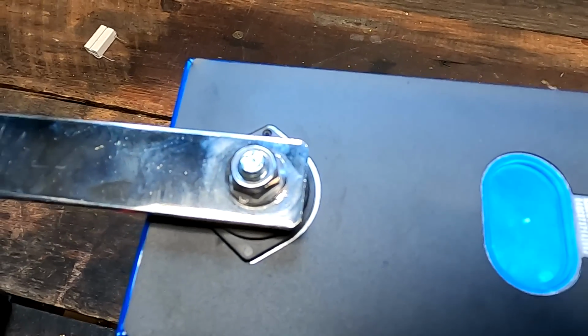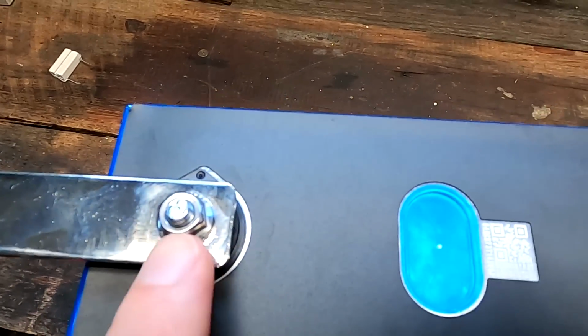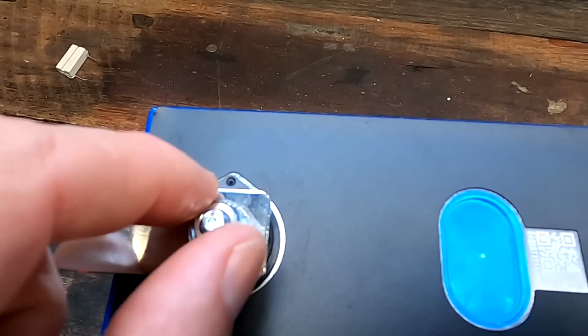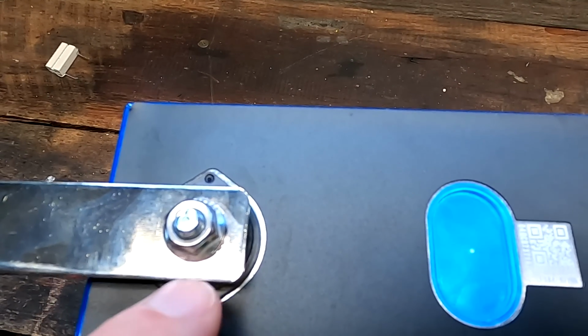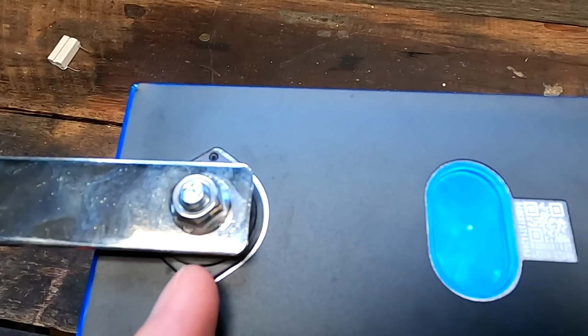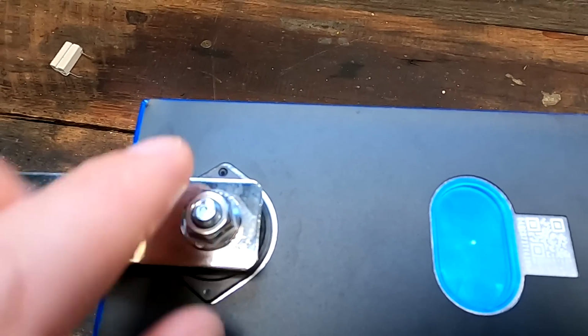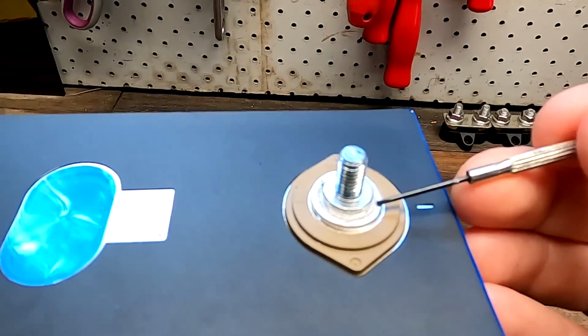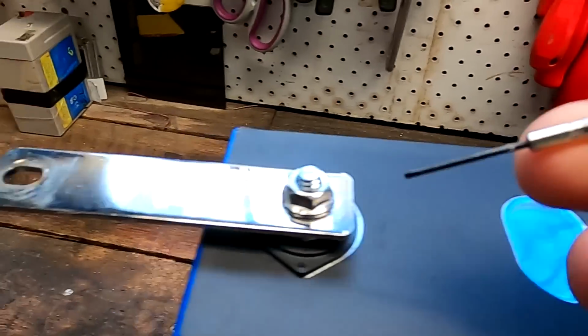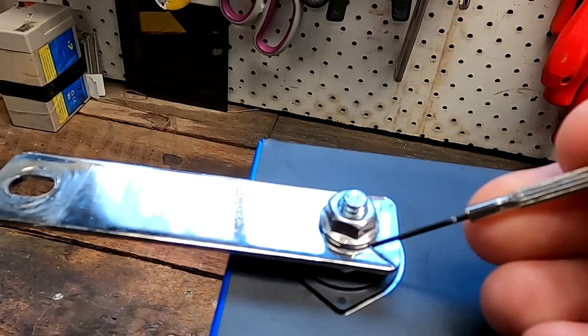Another frequent comment under the last video was that the flange nut at the top provides a fairly large contact area to the bus bar, which is why we don't see hotspots or heating. While this is true, I don't believe much current goes through the stud, from the terminal through the stud into the nut and back onto the bus bar. I really believe this is less than 5%, and I want to show you why I think this.